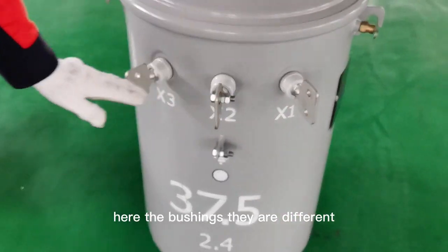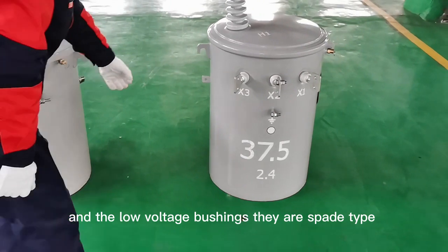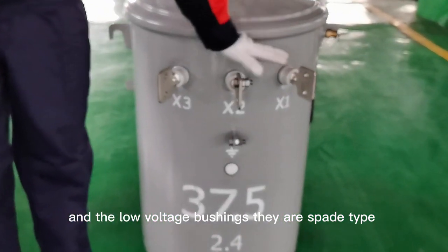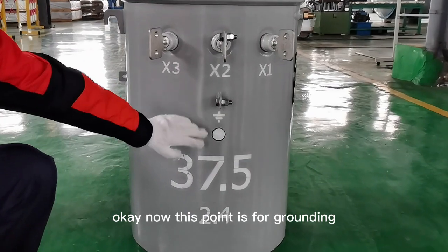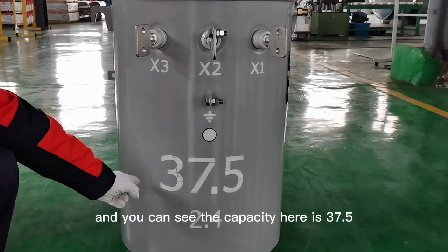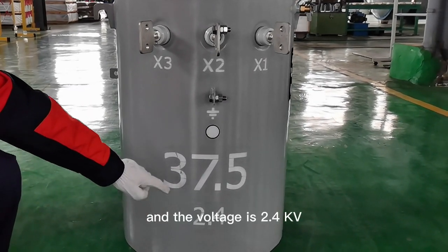The bushings are different on this one. This is the clamp type, and the low voltage bushings are spade type — they have two holes on the conductor. This point is for grounding. You can see the capacity here is 37.5 kVA and the voltage is 2.4 kV.